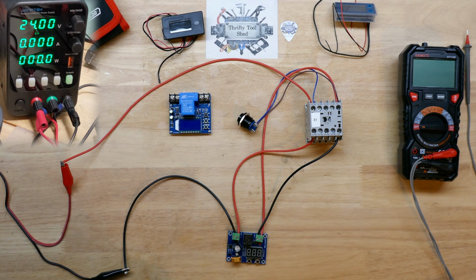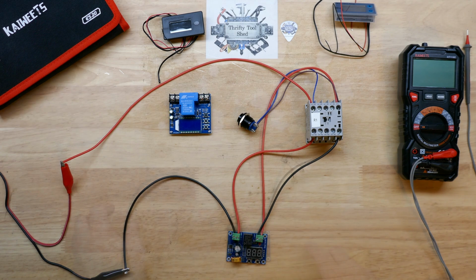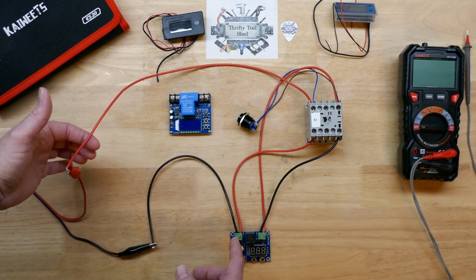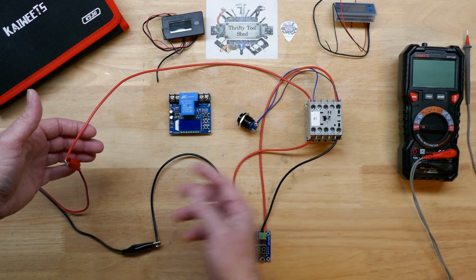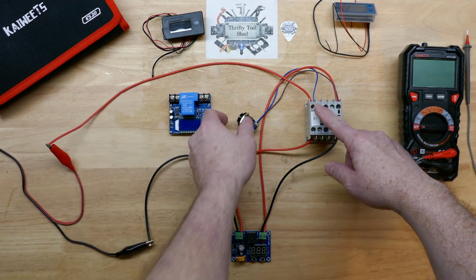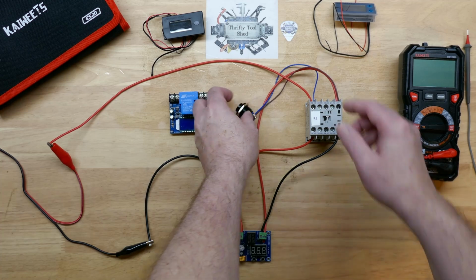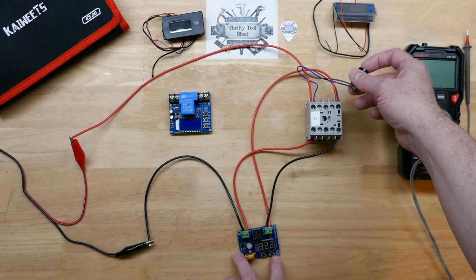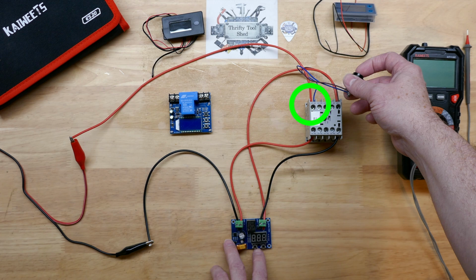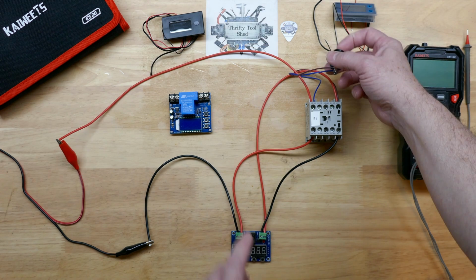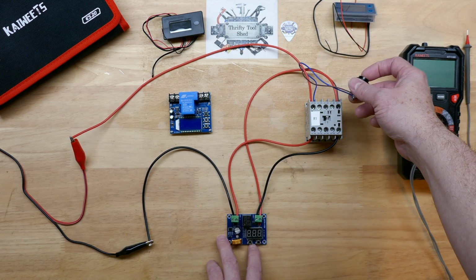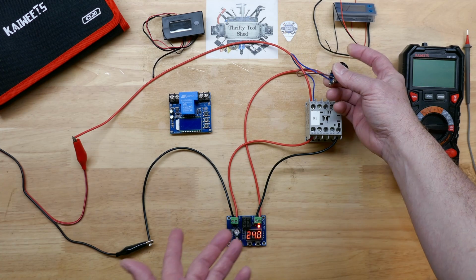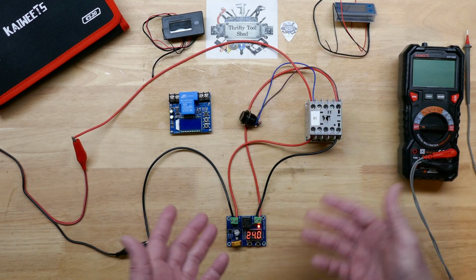So coming in on the leads here where my supply is hooked up will be your battery. And you see my board is not coming on. If you follow this around from the battery, it's just going here, and then it'll feed the board. But before this relay can pull in, if you'll see here, I have my push button across what will be the battery plus, and going over to my A1 on my coil plus on my 24 volt coil. So what you have to do is push this in and hold it long enough for the board to power up. As long as your voltage is high enough for it to pull in, you can let go of the button, and there you go.